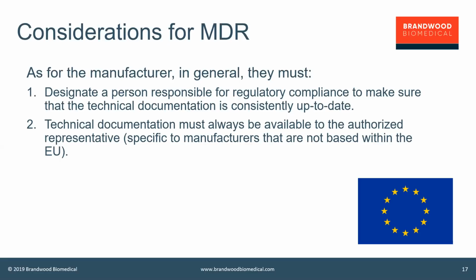The second one, it tends to be a little bit more for foreign manufacturers looking to sell into Europe, but is worth mentioning, and that's the expectation of the authorized rep to have all technical documentation readily available. Now, I say readily available because it's different than reasonably available. TGA will give you a fair amount of time to find that documentation. Although there isn't any defined timeline for when documentation needs to be able to be provided to a competent authority or a notified body from the authorized rep, the expectation is that that is within 24 to 48 hours.